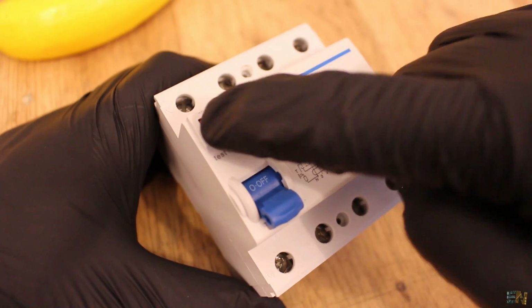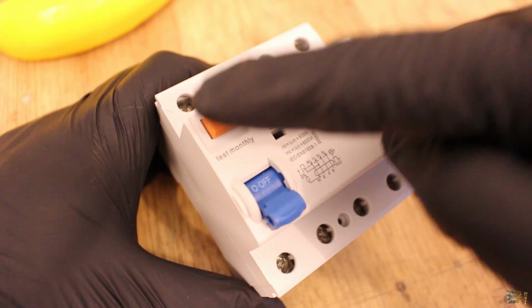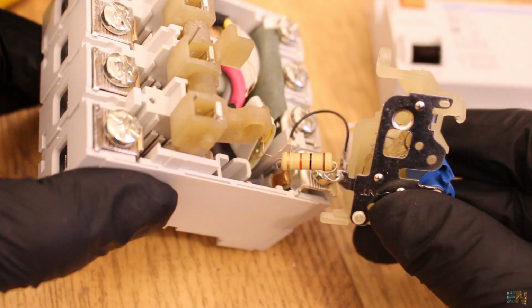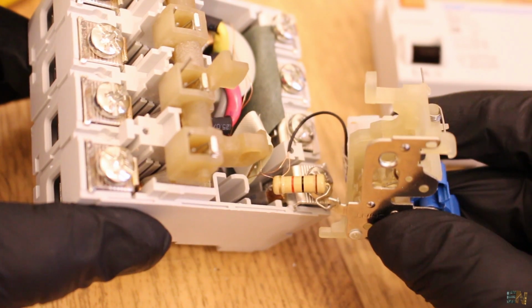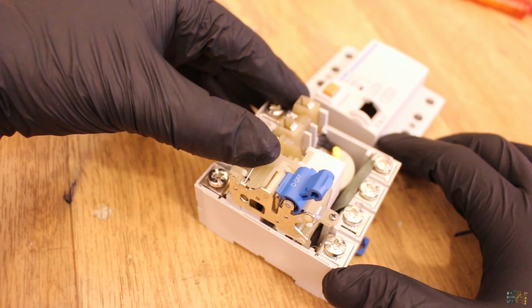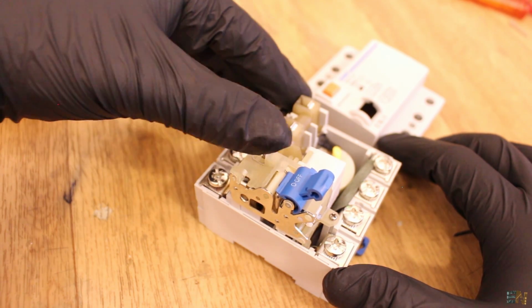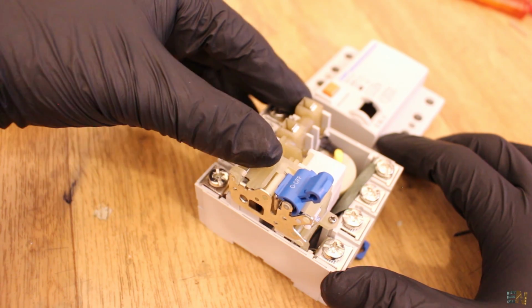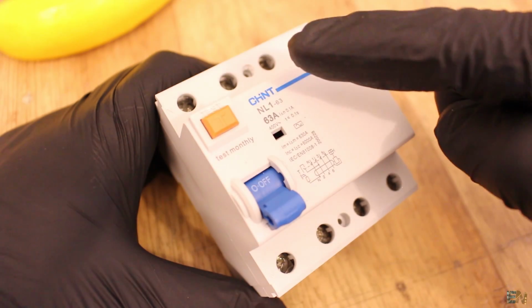The RCCB has a test button. Internally, this is connected to a small resistor, and when you push it, it will create a short circuit between the live and neutral through this resistor, and by that we simulate the residual current. We should test this monthly in order to see if the mechanism still works.